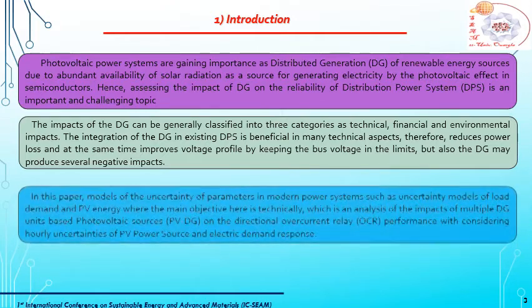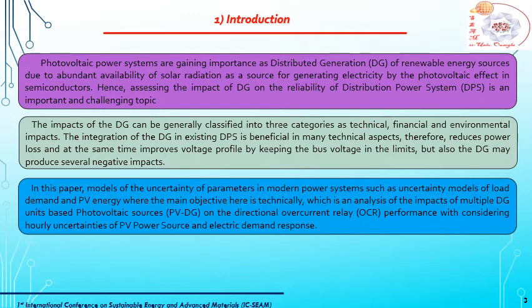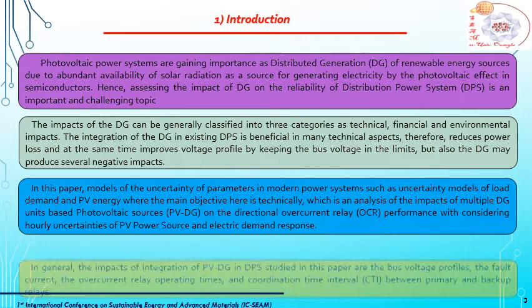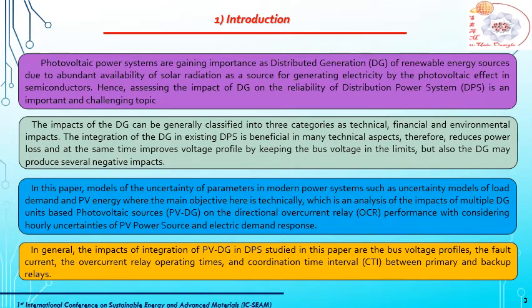negative impacts. In this paper, models of uncertainty of parameters in modern power systems, such as uncertainty models of load demand and PV energy, where the main objective here is technically, which is analysis of the impacts of multiple DG units based photovoltaic sources on the directional overcurrent relay performance with considering hourly uncertainties of PV power source and electric demand response. In general, the impacts of integration of PV-DG in DPS studied in this paper are the bus voltage profile, the fault current, the overcurrent relay operating time, and the coordination time interval between primary and backup relays.